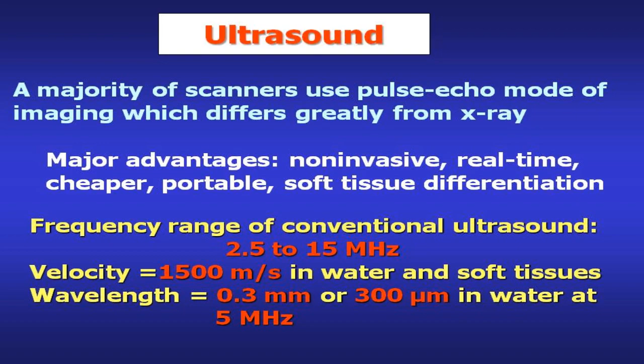So the idea, as I mentioned, is fairly simple. You have a device called a transducer that converts electrical energy into acoustic energy and vice versa. And suppose you have an object located in a water bath. Water is very important in this case. It serves as a coupling medium between the transducer and the body. So if you want to do this kind of examination in air, then you have to use an aqueous medium as the coupling medium, like gel.